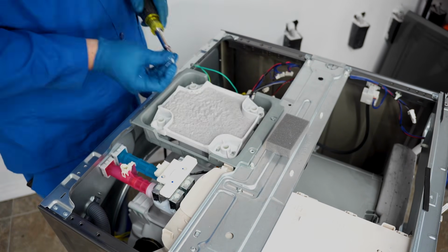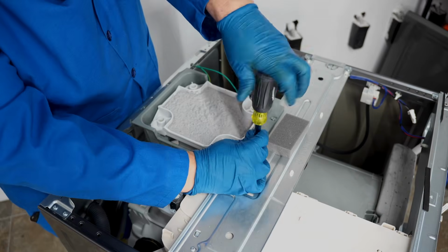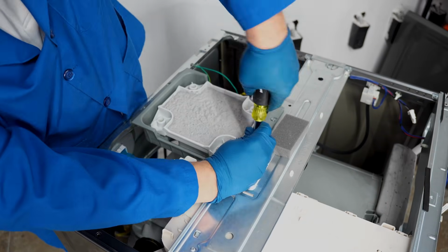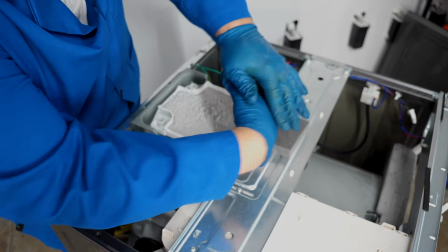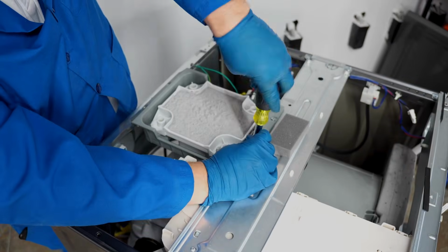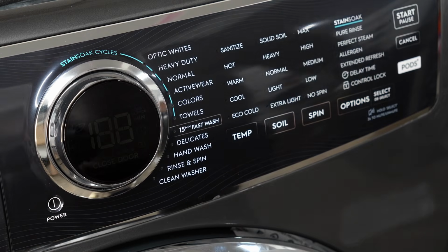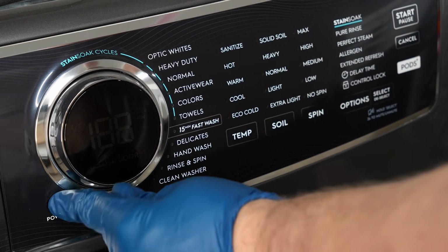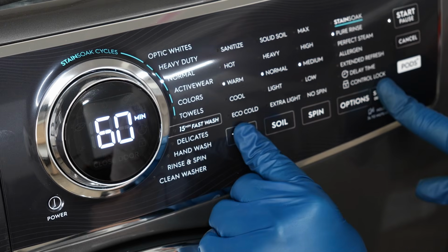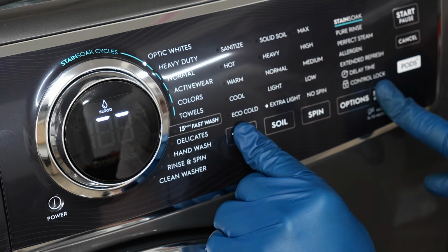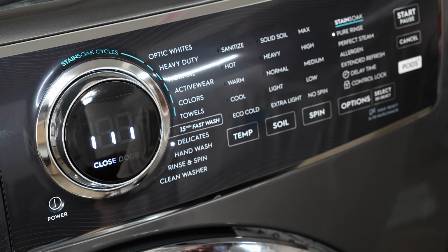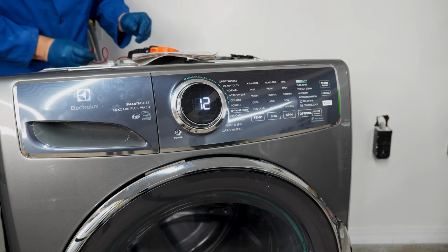The valves tend to be the issue in most situations, well, except maybe not. In some very rare cases, it's not the valves or the pressure sensor assembly, it's the control board that is failing. In this case, here's what you could try to do before you buy a new control board. With the unit installed with water and electricity but the top off, go back to the diagnostic mode that we used at the very beginning of the video.